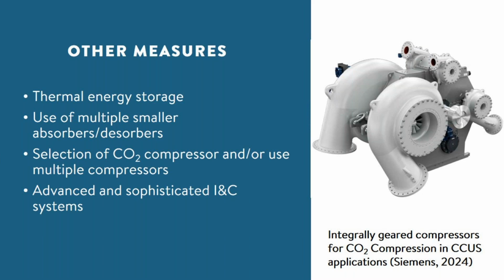Installing a thermal energy storage system can provide instant thermal energy to preheat the desorber reboiler during startup. Also, during peak demand, the stored thermal energy can be used for solvent regeneration and send all the steam from the steam generator to the steam turbine to increase the net power to the grid. The heat storage can be topped up during low load operation periods and/or prior to the power plant shutdown, and continue the regeneration operation in the desorber reboiler to treat residual flue gas.